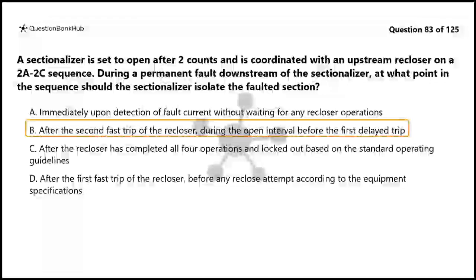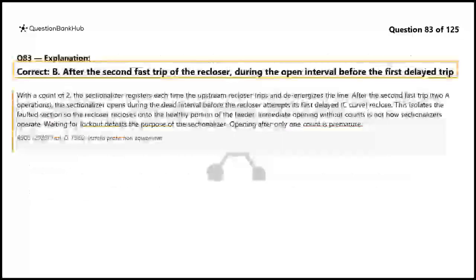The correct answer is B. With a count of 2, the sectionalizer registers each time the upstream recloser trips and de-energizes the line. After the second fast trip, 2A operations, the sectionalizer opens during the dead interval before the recloser attempts its first delayed, C-curve, reclose. This isolates the faulted section so the recloser recloses onto the healthy portion of the feeder. Immediate opening without counts is not how sectionalizers operate. Waiting for lockout defeats the purpose of the sectionalizer. Opening after only 1 count is premature.